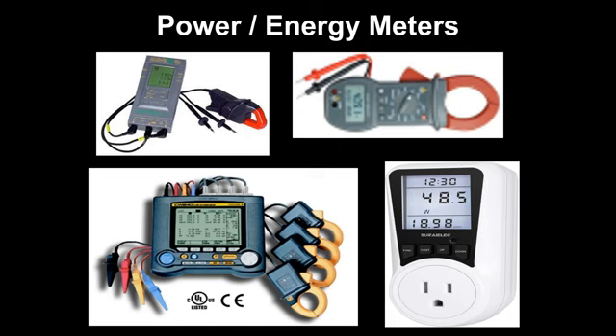It has a selectable switch, and then there are flexible CTs which can measure up to 6,000 amperes. They are available in different sizes. So depending on what measurement you are doing, you have to select the CT. You can have more than one set of CTs. Now we have 4 sets of CTs: 6,000 amperes, 3,000 amperes, 1,000 amperes, and this small one. Depending on where you want to do the audit, you can select the CTs. This is the enlarged version with 4 CTs. Because these are attachable CTs, you can select different rating CTs, same as the other meter.